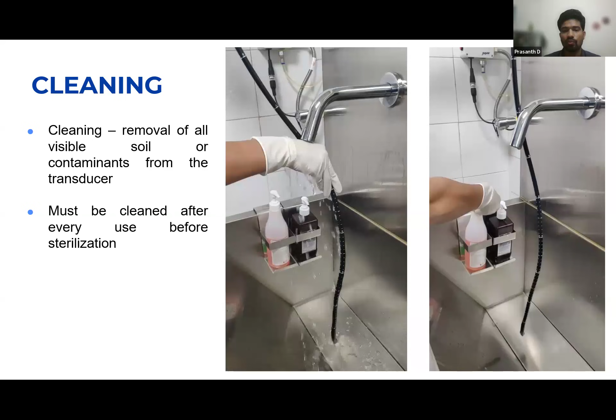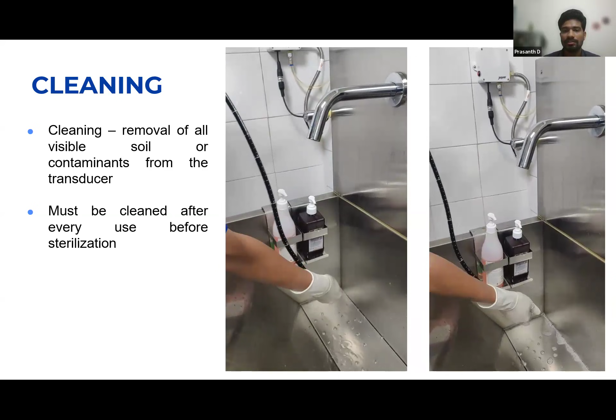Cleaning defines removal of all visible soil and contaminants from the transducer. It must be cleaned after every use before sterilization. After removing and wiping off, we have to clean with running water for about 1 minute. After that, detergent should be used for cleaning. The water should not touch the control housing. Only the tip and the shaft of the TEE probe should be cleaned with water and detergents. After that you have to rinse and dry it properly.